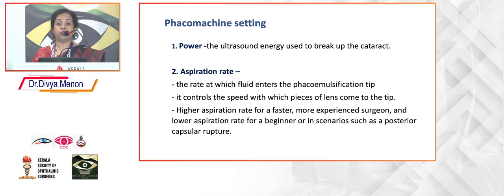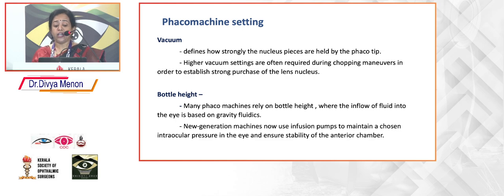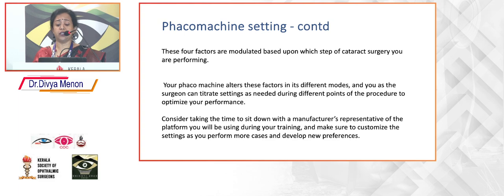A higher aspiration rate can be kept for a faster and experienced surgeon, but as a beginner, it is always advisable to go for a low AFR, and in scenarios where you have PCRs. Vacuum defines how strongly the nucleus pieces are held by the phaco tip. Higher vacuum settings are often required during the chopping maneuvers in order to establish a strong purchase of the lens nucleus. Many phaco machines rely on bottle height, where the inflow of fluid into the eye is based on gravity fluidics. So depending upon the cataract and depending upon the eyes, you have to adjust your bottle height. Newer mid-generation machines now use infusion pumps to maintain a chosen IOP in the eye and for anterior chamber stability. So these four factors are modulated based upon which step of cataract surgery you are performing.